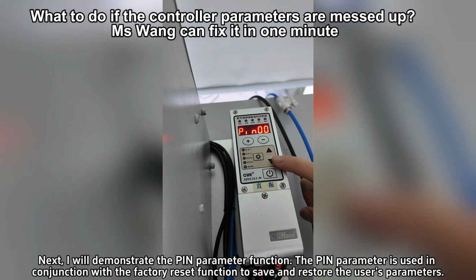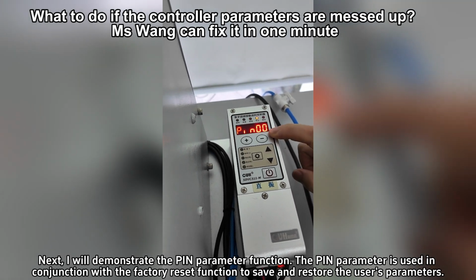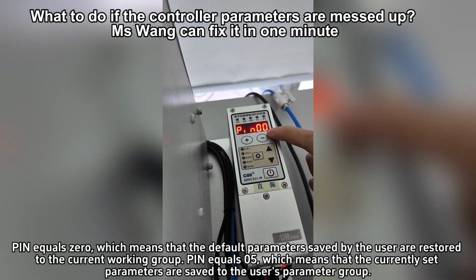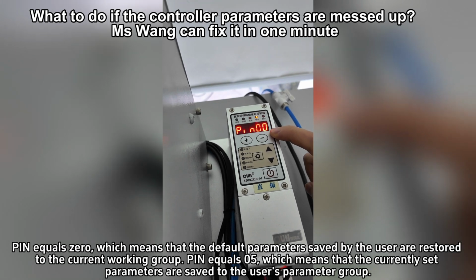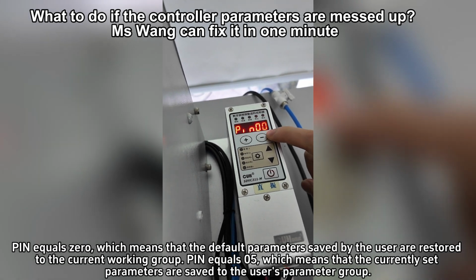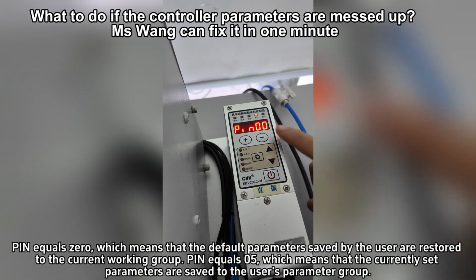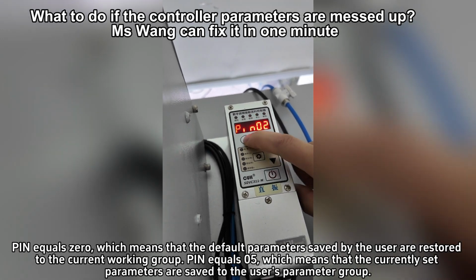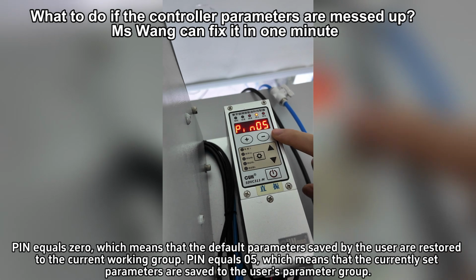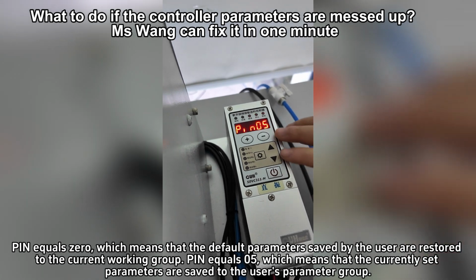The pin parameter is used in conjunction with the FactoryReset function to save and restore the user's parameters. Pin equals 0 means that the default parameters saved by the user are restored to the current working group. Pin equals 05 means that the currently set parameters are saved to the user's parameter group.